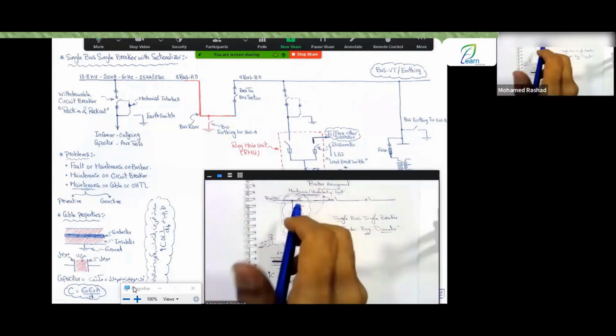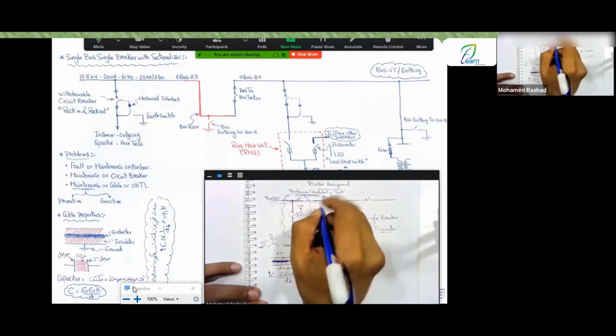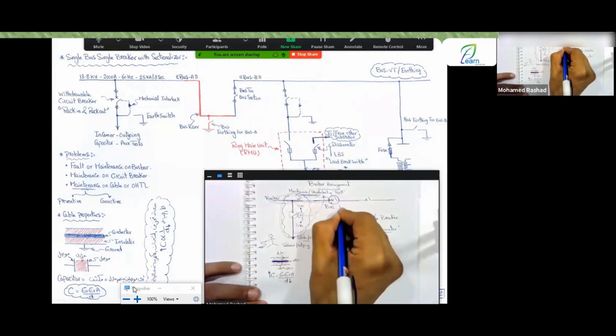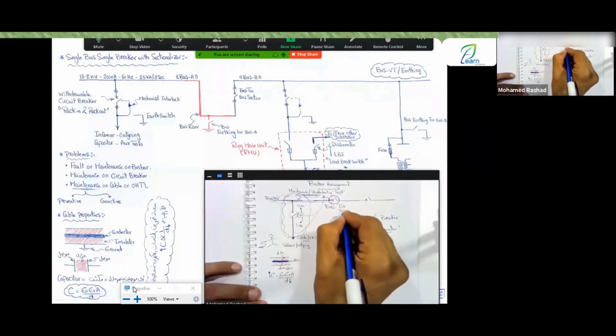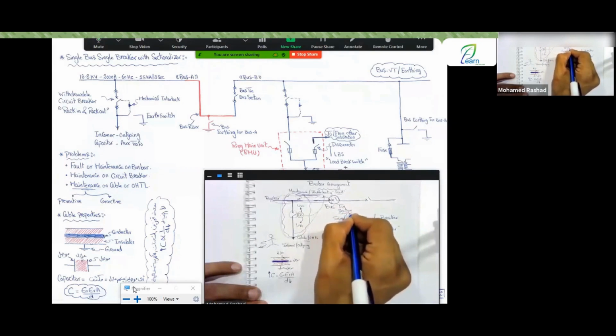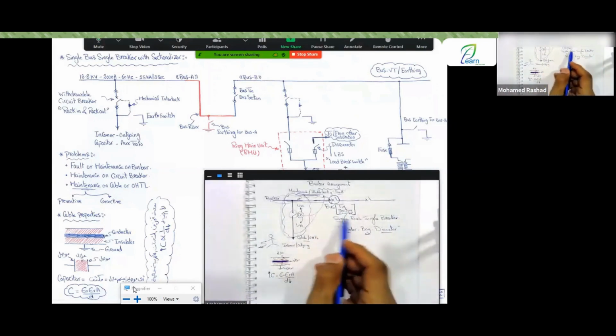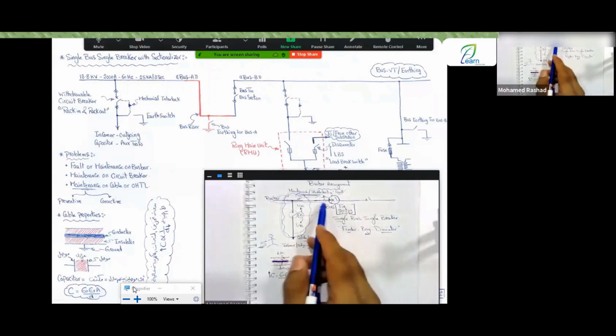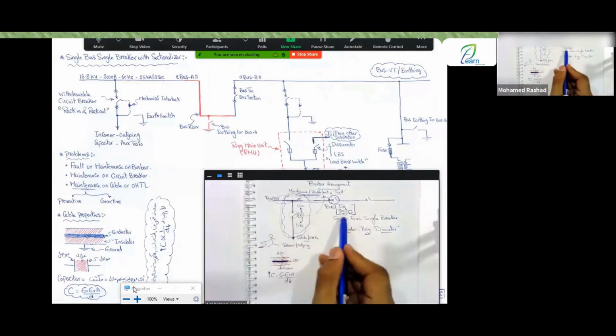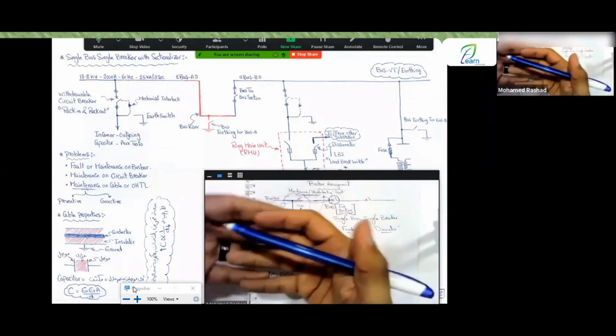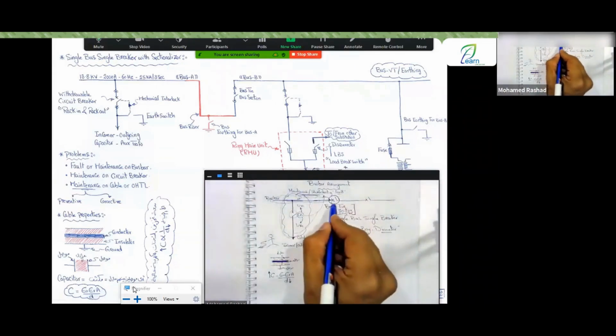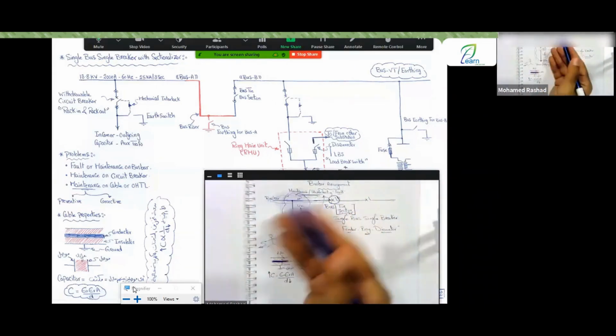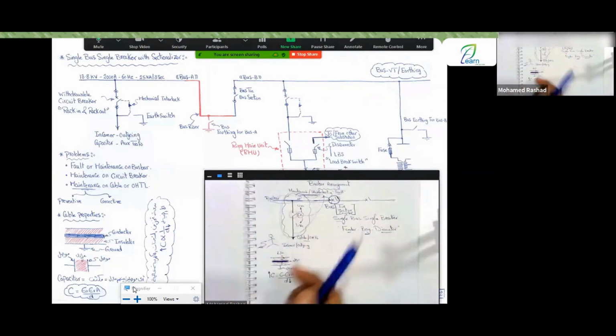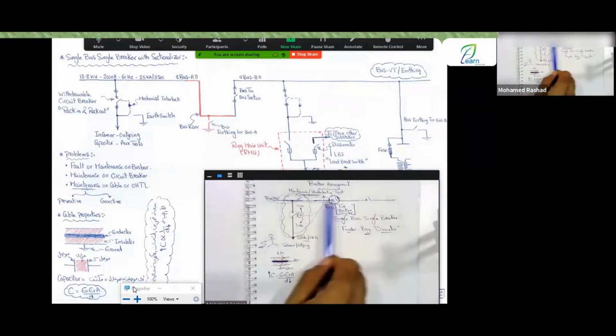He said, look, quite simply, between each bar and the next, I will install an electrical breaker, and I will name this electrical breaker either tie, which comes from the necktie, or section, or coupler, depending on what each of you calls it in the place where you work. In the end, this breaker is an electrical breaker, and its function is simply to be a tie, a section, or a coupler. This necktie is what connects one thing to another, or a section as a result of dividing this bar into 2 sections. Or there are 2 different bars, so you create coupling between them by connecting the 2 together. In this case, what is the purpose of this breaker? The purpose of this breaker is to close in order to allow for the sharing of power, meaning the sharing of your power capacity between the bus bar and the other bus bar.